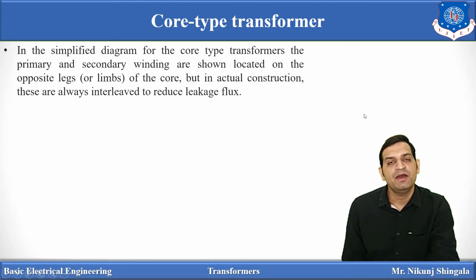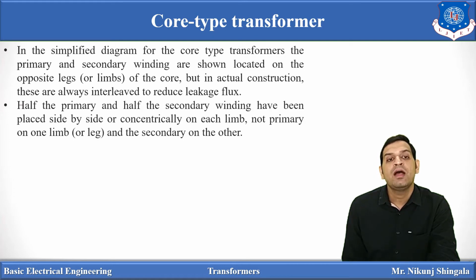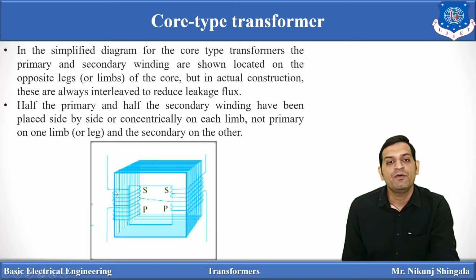We see that the primary winding and secondary winding are placed on opposite limbs, but in actual construction, they are always interleaved to reduce the leakage flux. Because if primary and secondary are placed on opposite limbs, there will be a leakage flux. So to minimize the leakage flux and provide tight coupling between primary and secondary winding, half of the primary winding and half of the secondary winding are placed side by side, concentrically on each limb, and not primary on one limb and secondary on the other limb. Here you can see half of the primary winding is placed over here and half of the secondary winding is also placed on one limb. So both limbs consist of primary and secondary winding, and both are concentric windings.